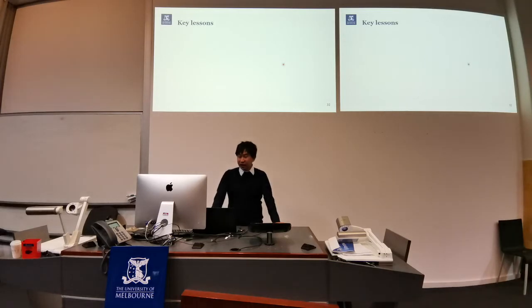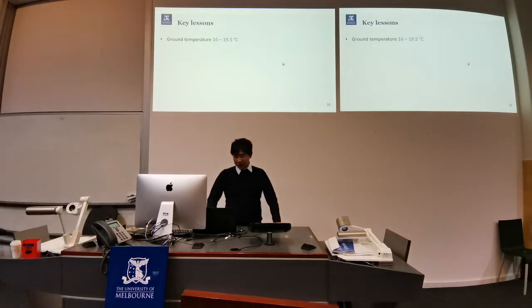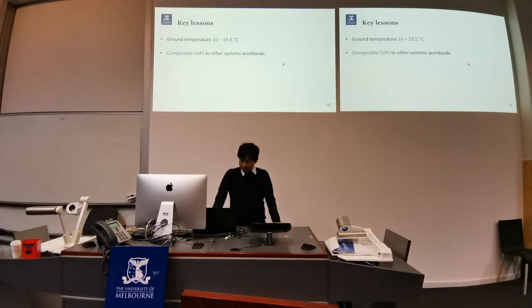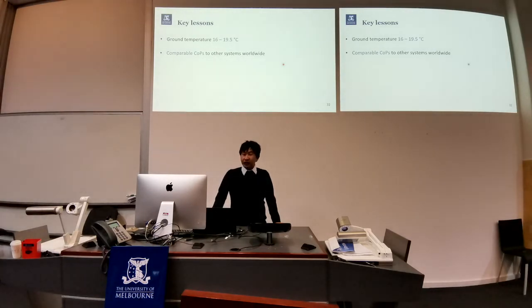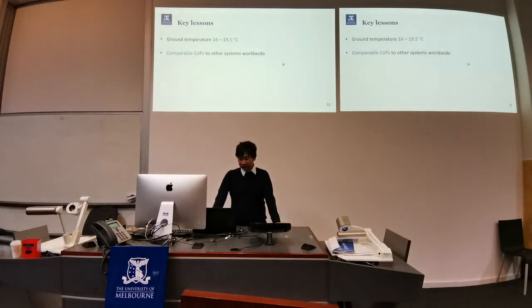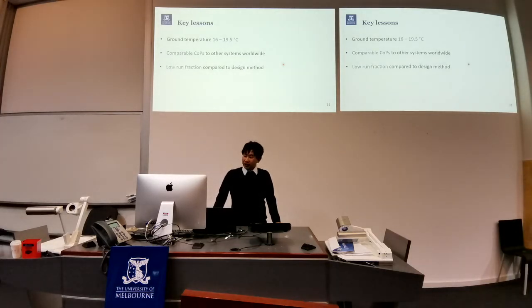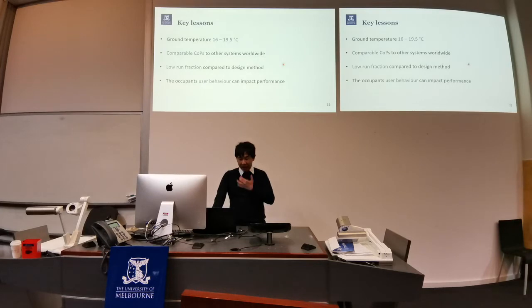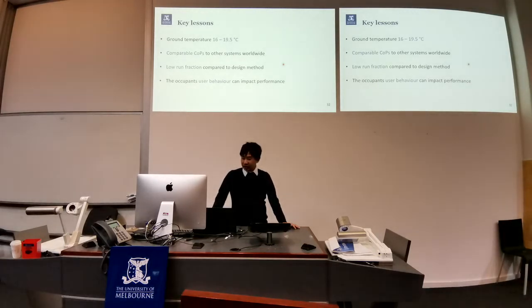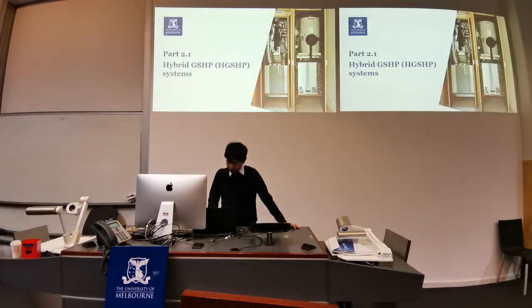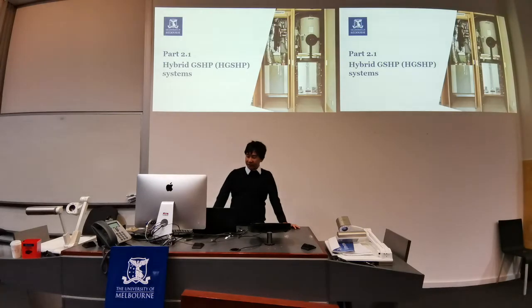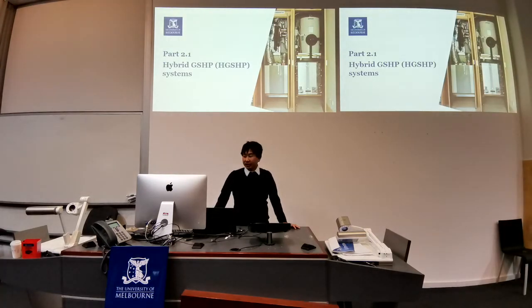So this leads to some key lessons that we have learned during this project. Firstly, the ground temperature varies more than we originally thought, from 16 to 19.5 degrees Celsius. The efficiency of the systems that we monitored is comparable to other systems worldwide. However, the properties that we monitored have a relatively lower run fraction than what is expected. Finally, user behavior might impact the performance of the system. A low usage may be good when the ground temperature can stay relatively constant. However, an energy efficient system might not yield much financial benefit if it's barely used. This leads to the second topic, where such a hybrid system may be beneficial in Australian temperate climatic conditions.